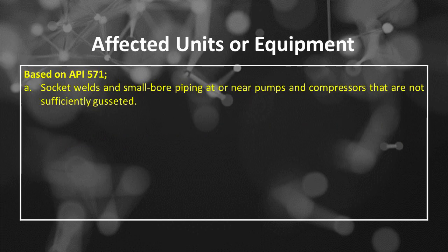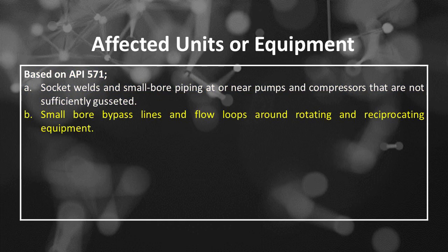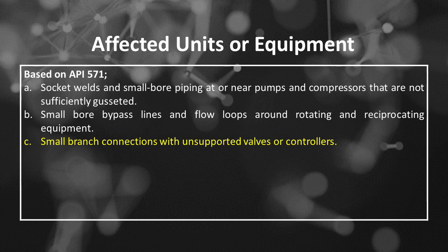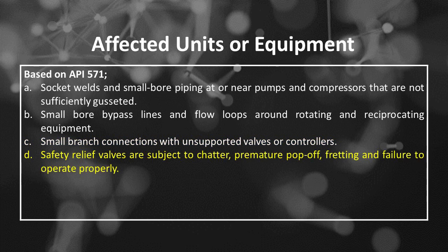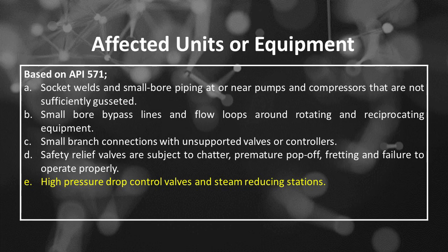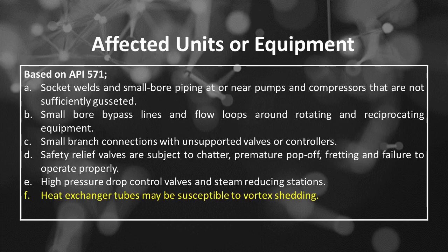Vibration-induced fatigue damage mechanisms affected units or equipment based on API 571. The first is socket welds and small-bore piping at or near pumps and compressors that are not sufficiently gusseted. The second is small-bore bypass lines and flow loops around rotating and reciprocating equipment. The third is small branch connections with unsupported valves or controllers. The fourth is safety relief valves subject to chatter, premature pop-off, fretting and failure to operate properly. The fifth is high-pressure drop control valves and steam-reducing stations. The sixth is heat exchanger tubes that may be susceptible to vortex shedding.